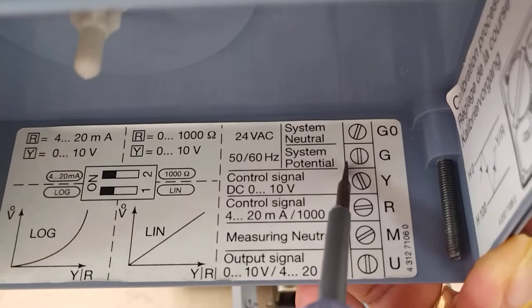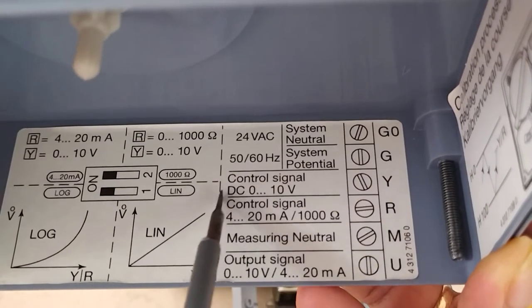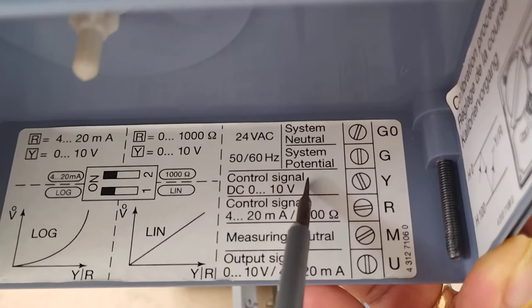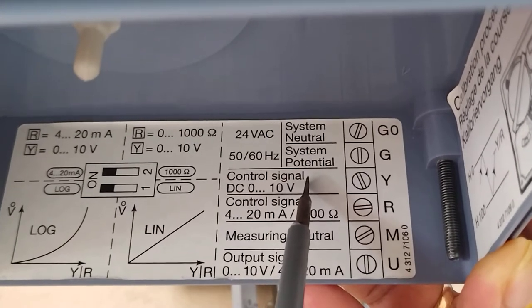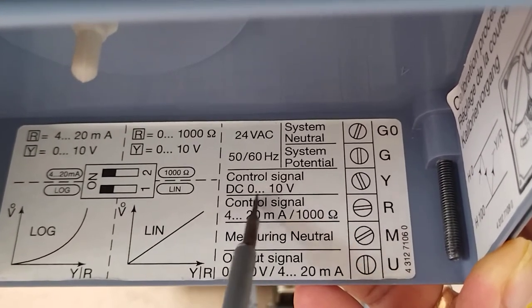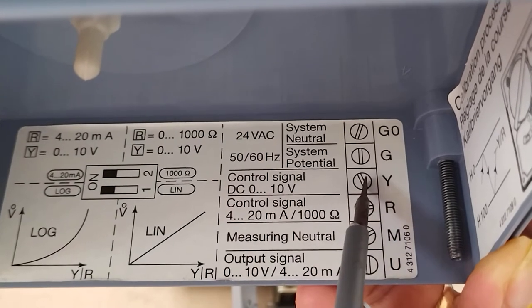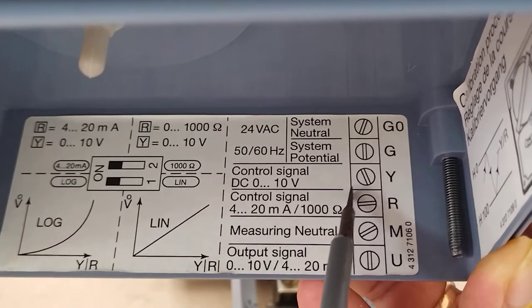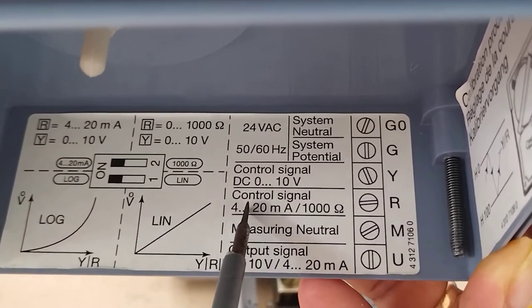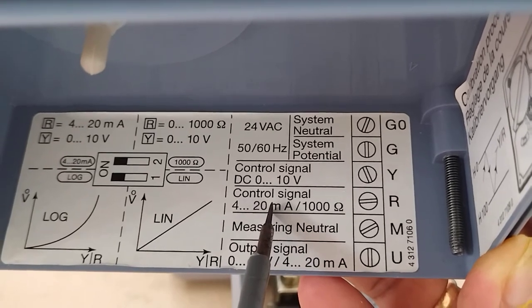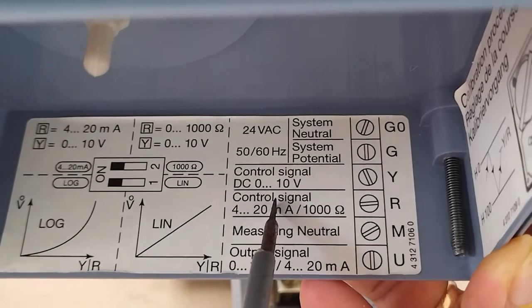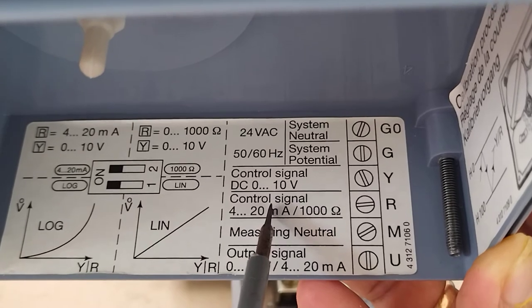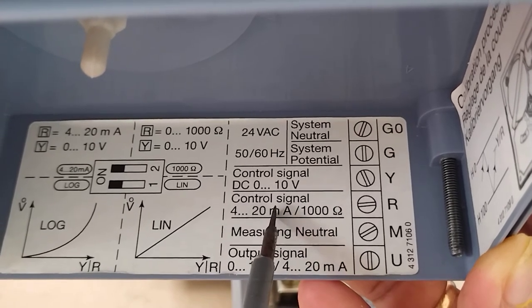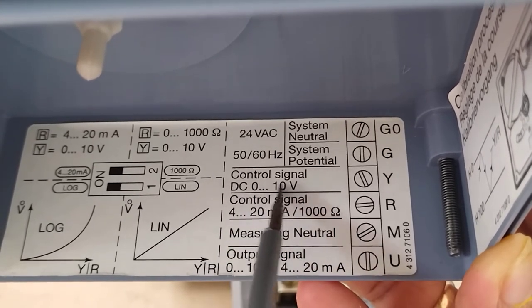Then the control signal, as I said, will be the one that opens and closes the valve in a modulating way, from 0 to 10 volts. You can also provide the control signal as 4 to 20 milliamps, but in my experience I seldom encounter the current signal — we always use the 0 to 10 volt signal.